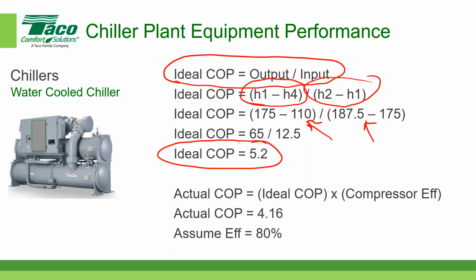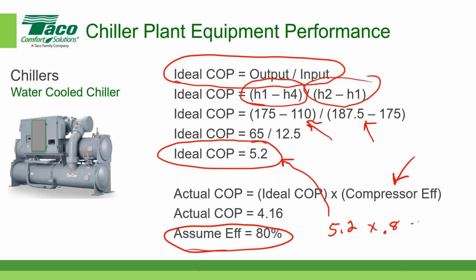And that's reduced, because the actual COP also includes the compressor efficiency. And if we put in there an efficiency of 80%, then 80% of 5.2, which is this value from up here, times 0.8 is going to be equal to 4.16.